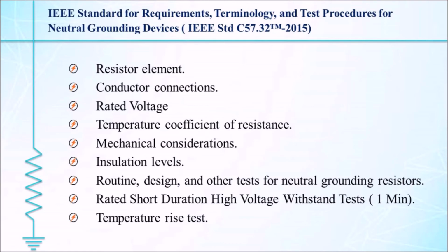Celsius. This is to help ensure that the final fault current has a value sufficiently high to allow the protective circuitry to operate as intended. It is recommended that neutral grounding resistors rated less than continuous duty should be equipped with a resistor monitor to verify the tolerance and continuity of the resistance. The resistor shall be monitored continuously.